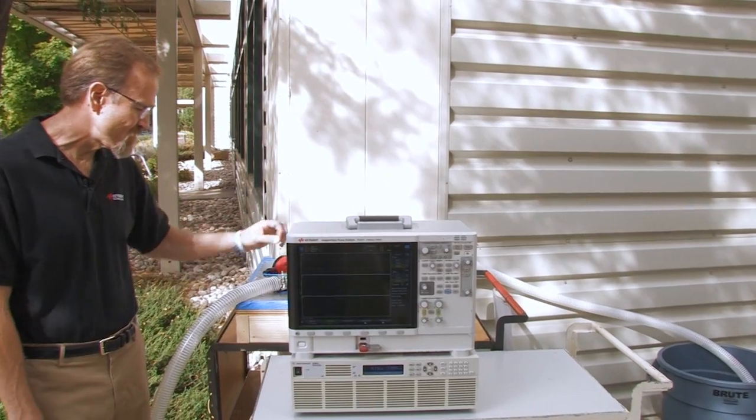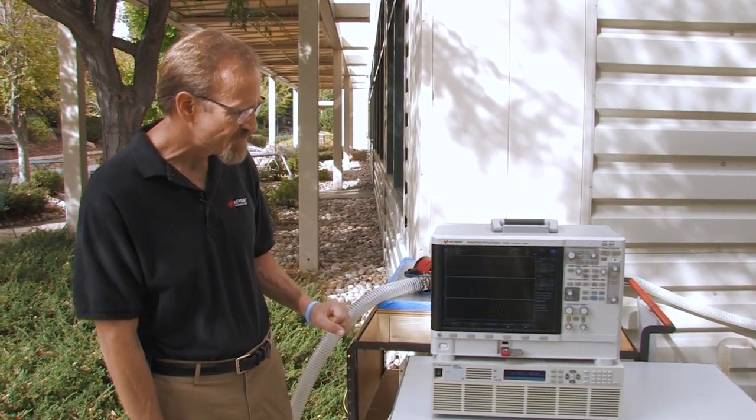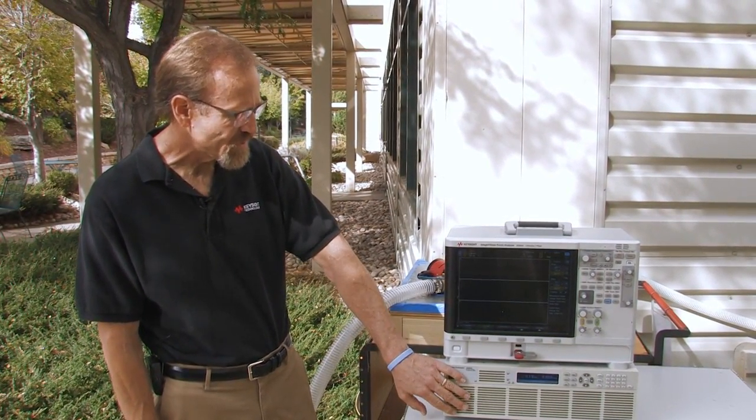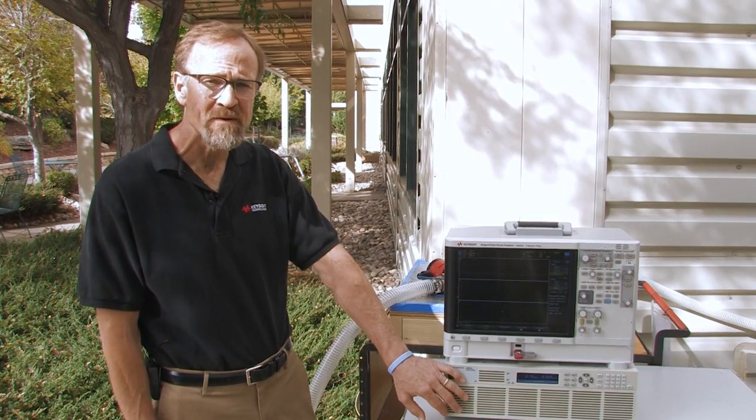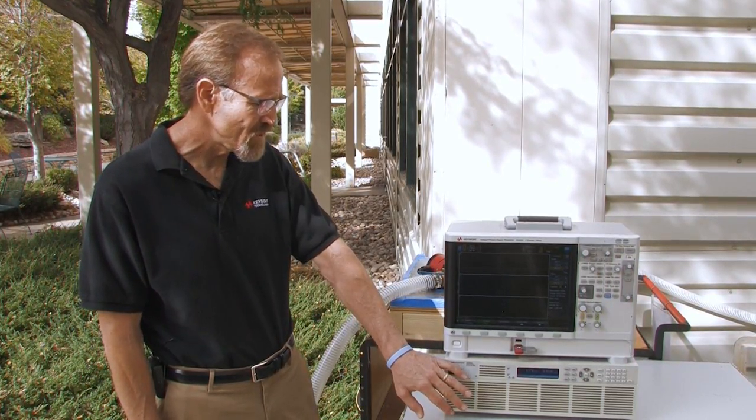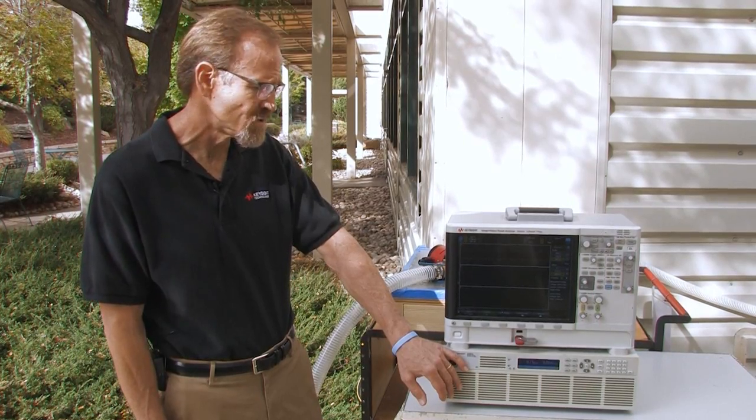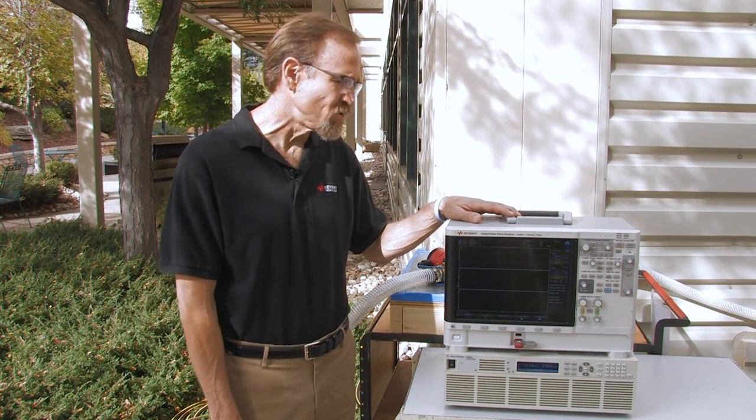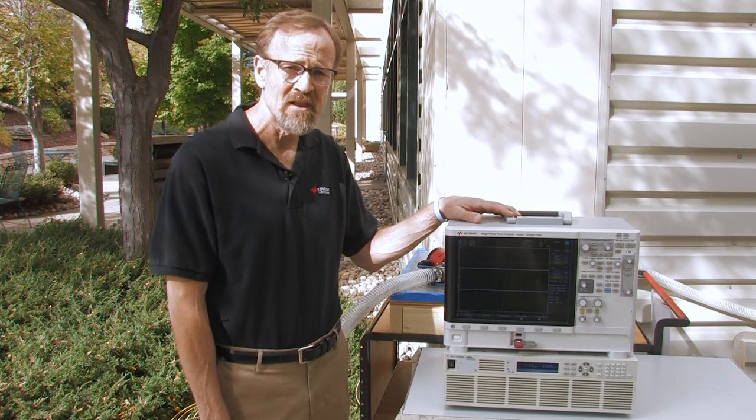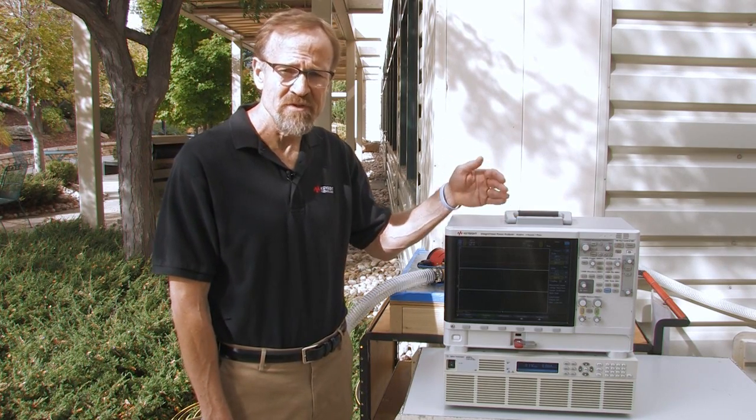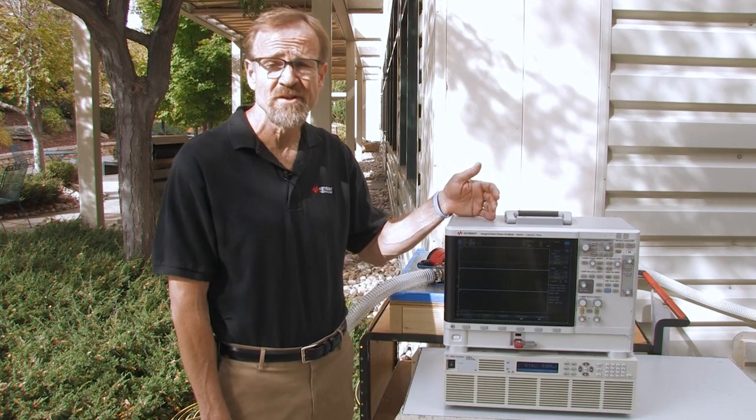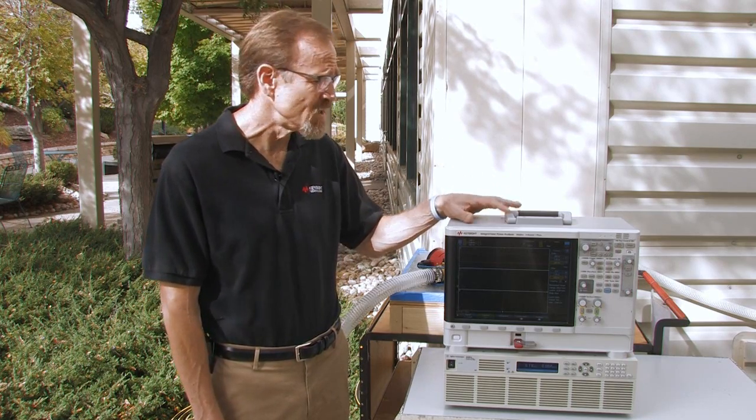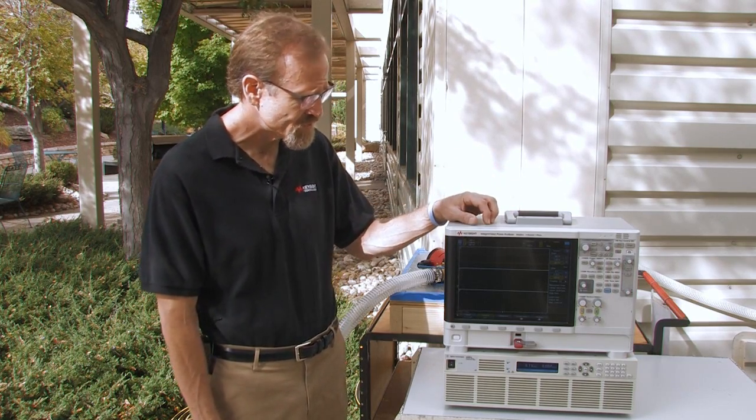The way we have the pump connected to our instrumentation is first we're using an AC power source to power up the pump. This is a European pump so we need 230 volts input, and then we have it directly connected to channel one of the IntegraVision power analyzer. Both the voltage and the direct connect to the current, we have a 50 amp range, and that's how we have it connected, so no transducers are necessary.